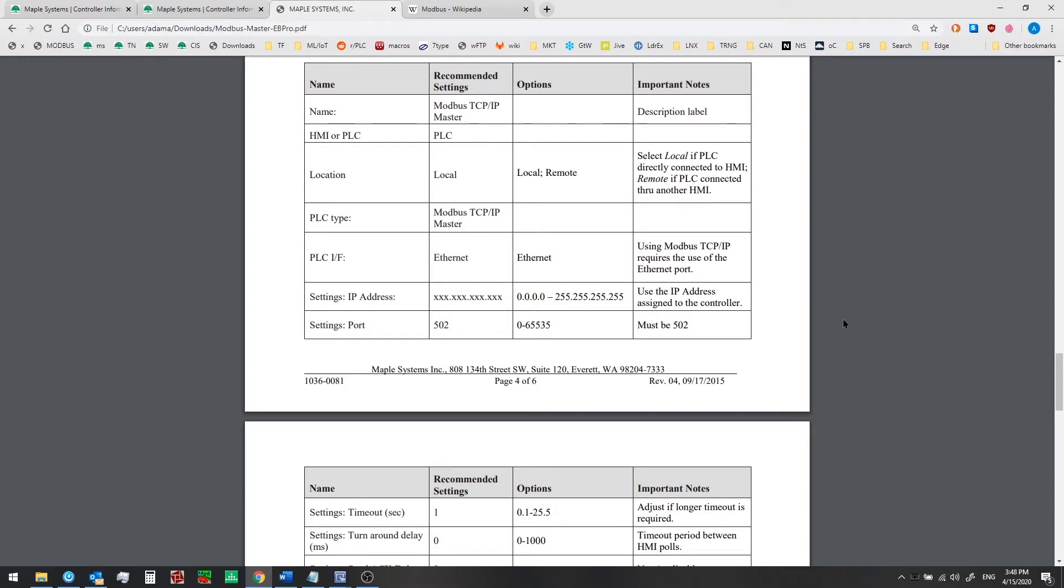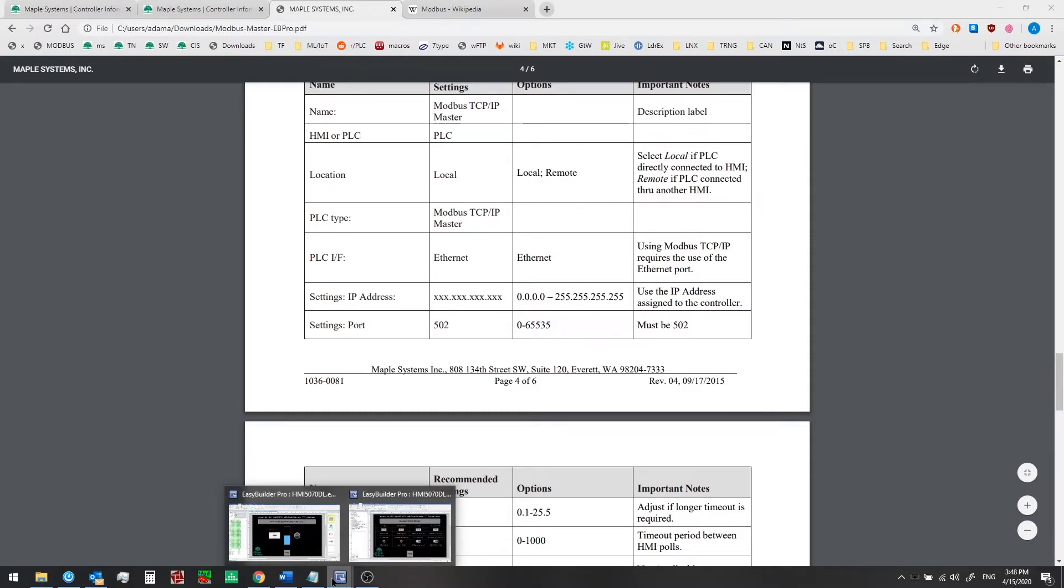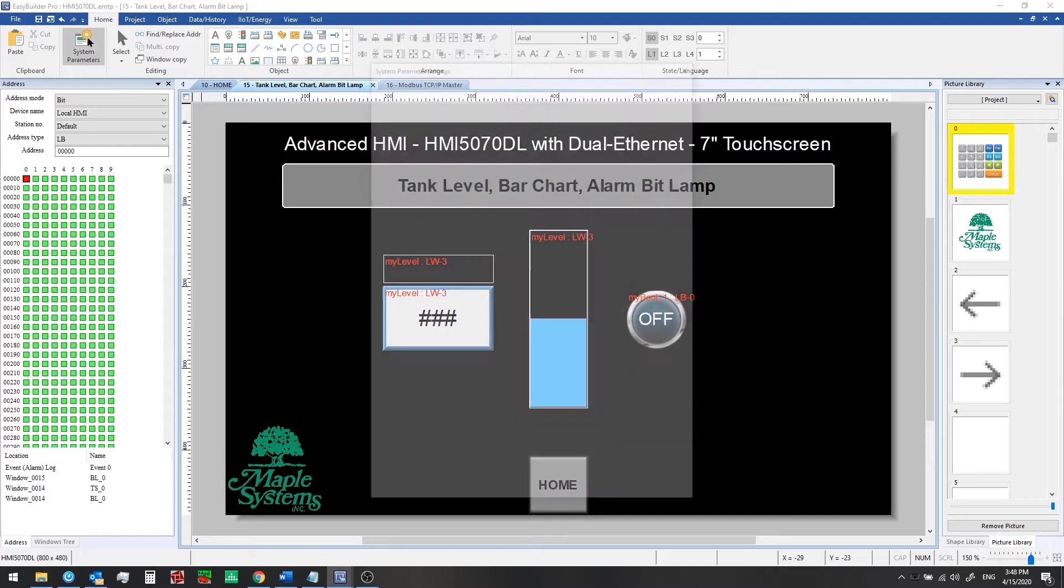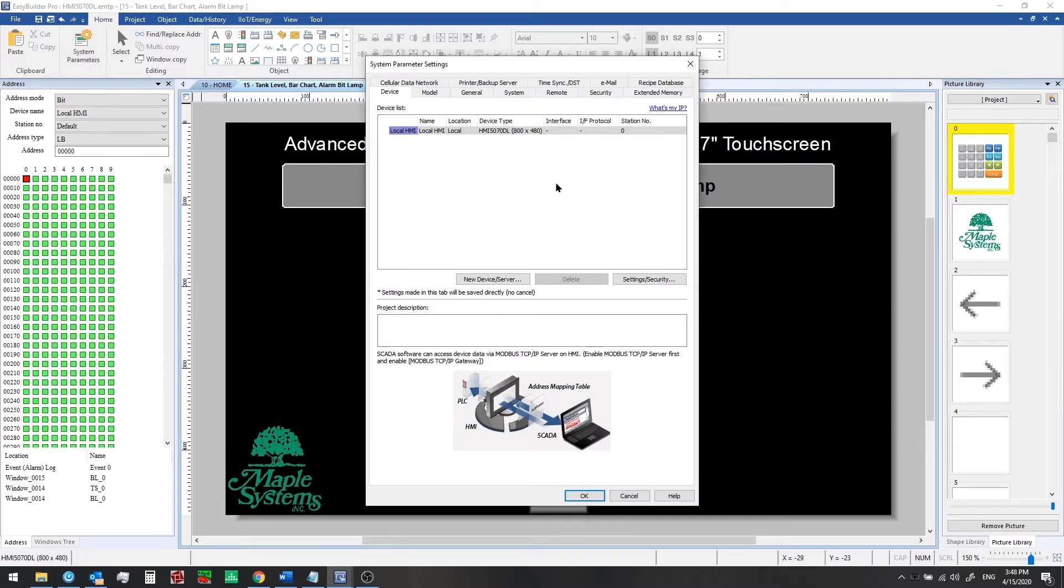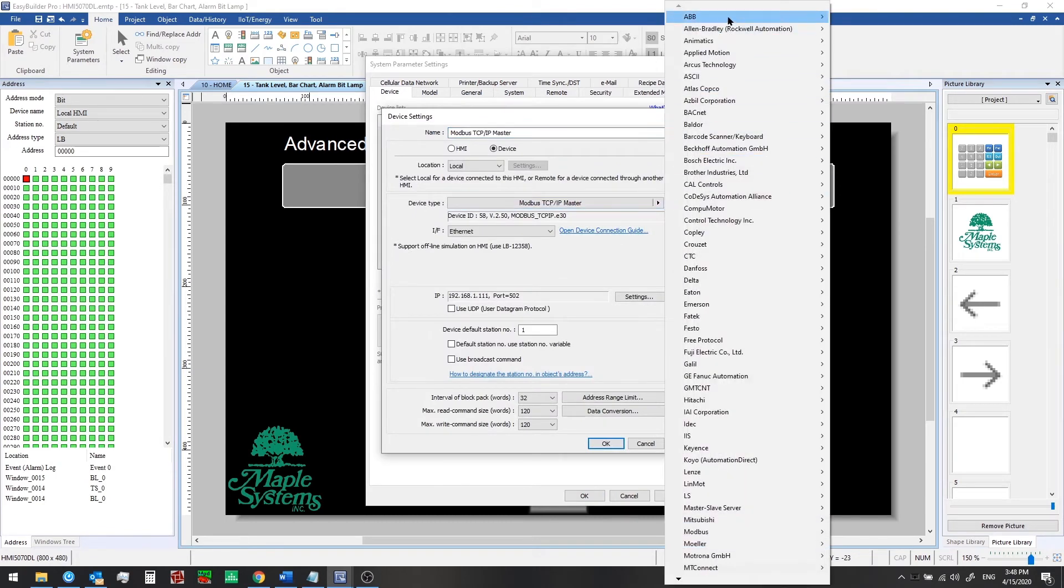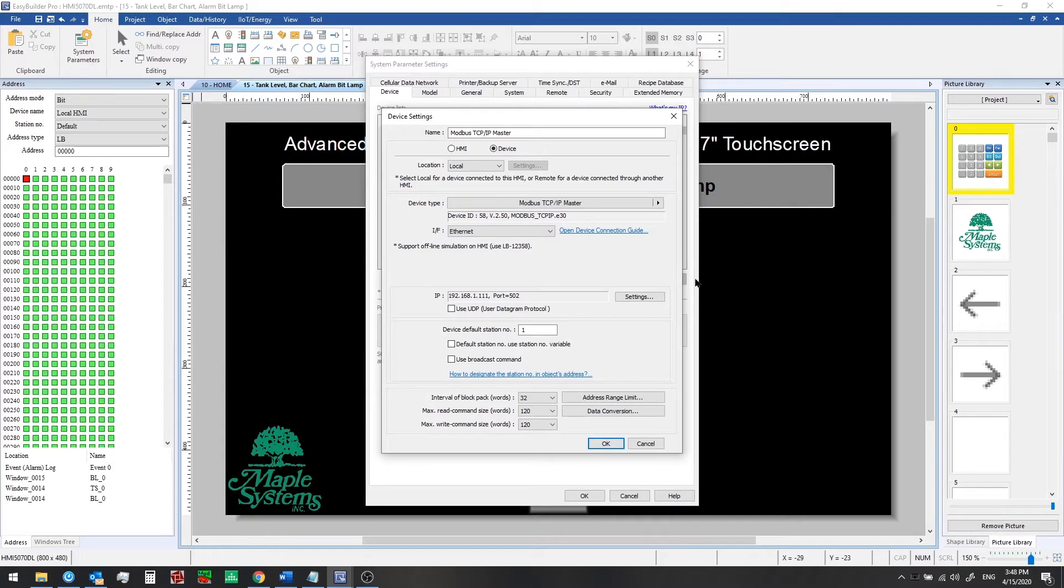Now let's go back to EB Pro and we'll add a communication driver. We're going to go to the home tab and click on system parameters. We have just one device listed, which is our local HMI. Now we can click on the new device or server button. From device type we can select from a long list of manufacturers and types of protocols. Modbus TCP IP master is what we're going to use here. So the HMI will be the master and the Modbus device will be the slave in this situation, and the interface is Ethernet.